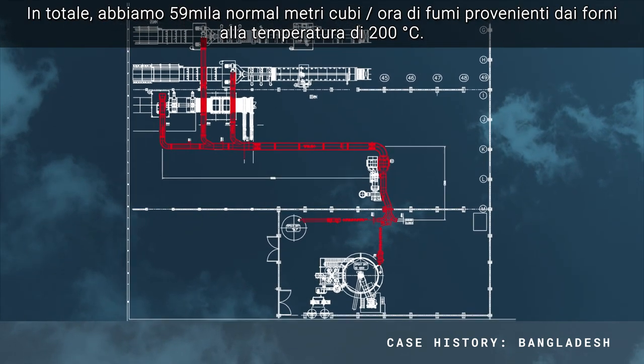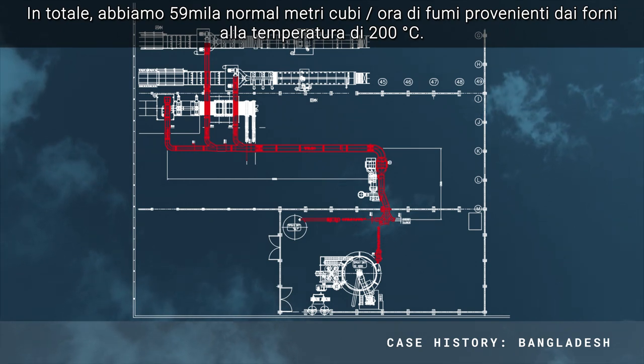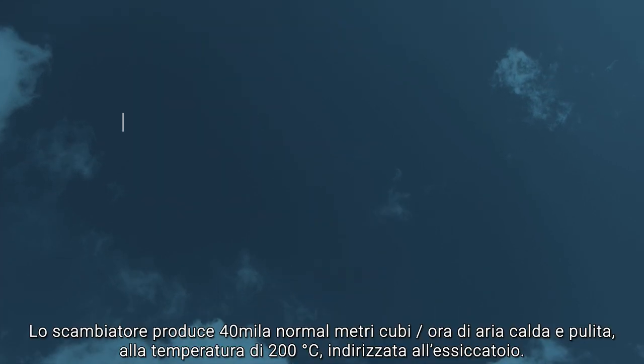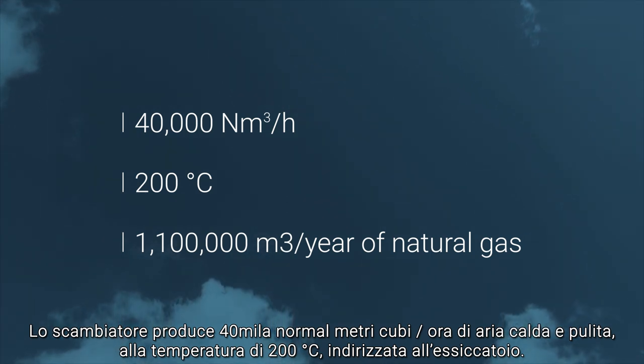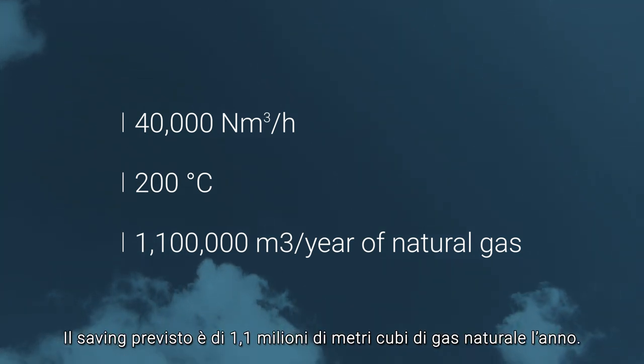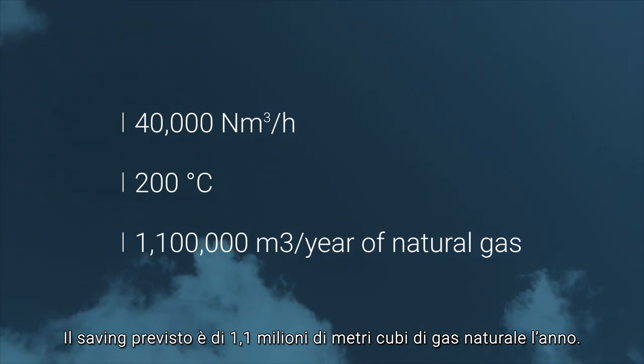A total of 59,000 normal cubic meters per hour arrives from the kilns at a temperature of 200 degrees. The heat exchanger produces 40,000 normal cubic meters per hour of clean hot air at a temperature of 200 degrees, which is sent to the spray dryer. Savings are calculated to be 1.1 million cubic meters of natural gas per year.